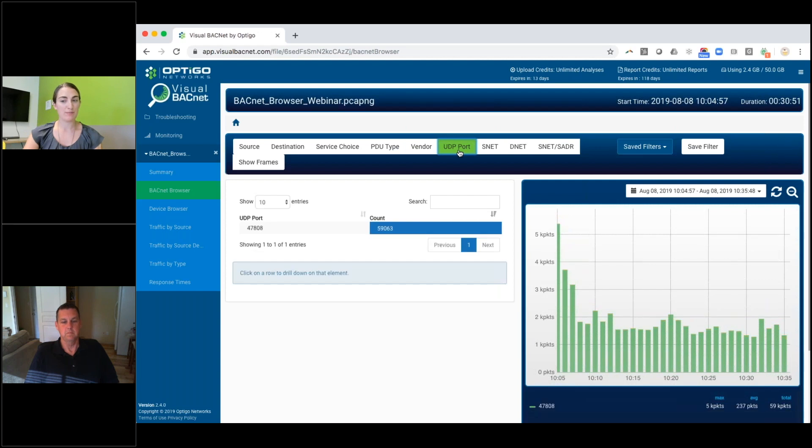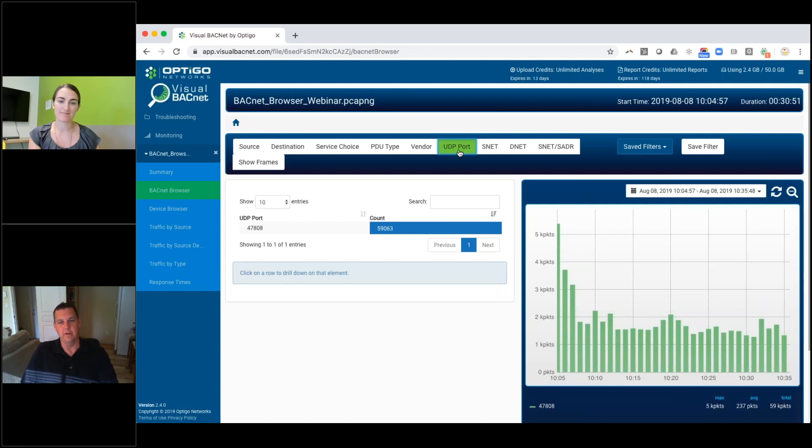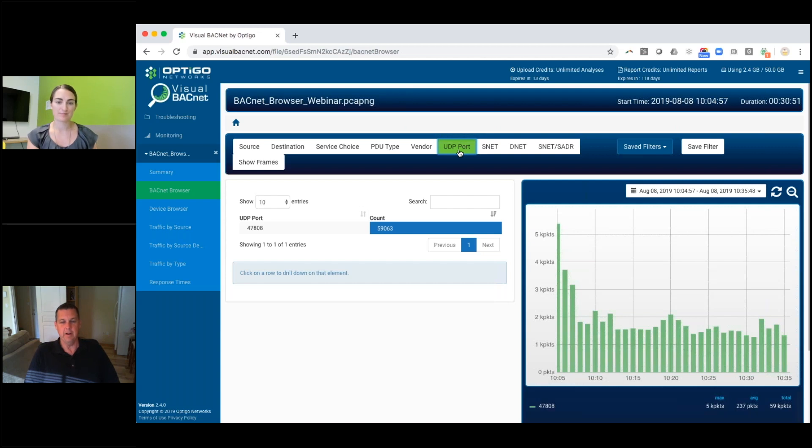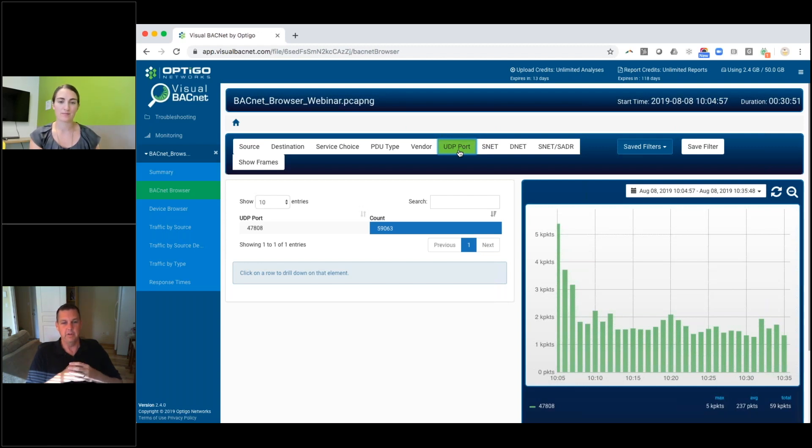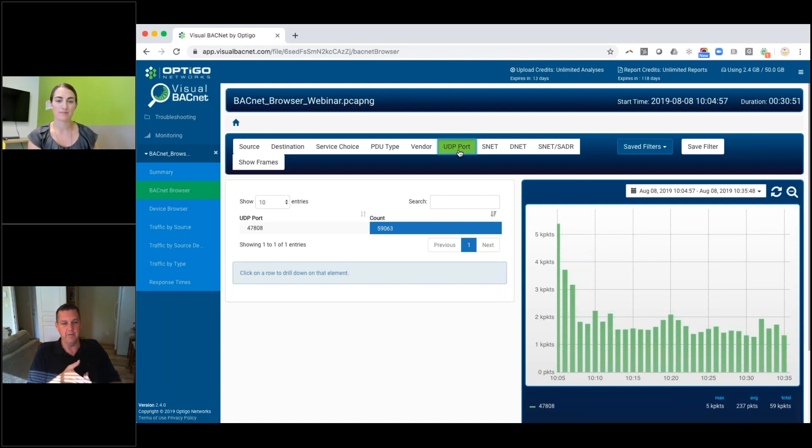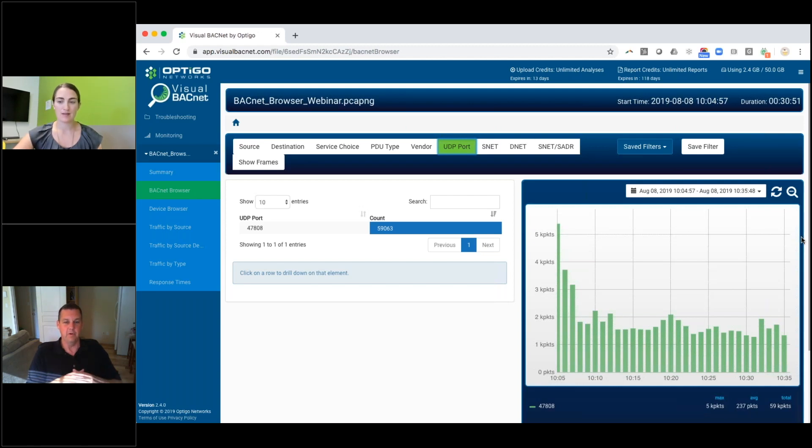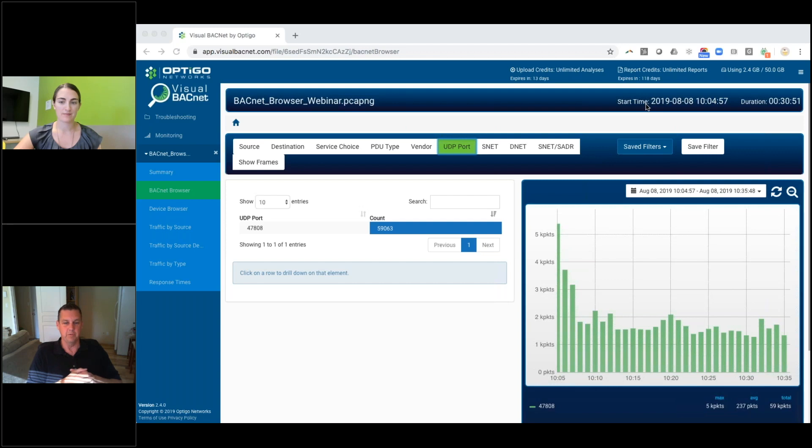UDP port, Ryan? Again, with the UDP port, another way to look at your site and see how it's segmented. As we know, everything on one UDP port, such as 47808, everything can talk very easily and simply. If you have multiple UDP ports, then you're not always crossing traffic. So it's a way to see how segmented is the site. Is everyone talking? Is this particular UDP port completely overloaded? It gives you some more information. And again, it's another way that you can troubleshoot in a different way.